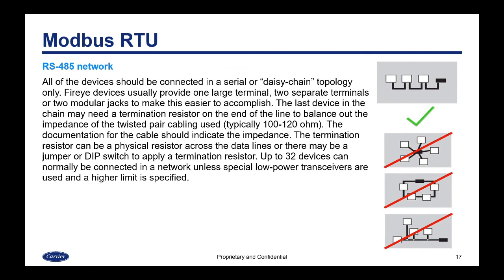All of the devices should be connected in a serial or daisy chain topology. Fireye devices usually provide one large terminal or two separate terminals or two modular jacks to make this easier to accomplish. The last device in the chain may need a termination resistor on the end of the line to balance out the impedance of the twisted pair cabling used. This impedance is typically 100 to 120 ohms. The documentation for the cable used should indicate the impedance. The termination resistor can be a physical resistor across the data lines, or there may be a jumper or DIP switch to apply one.